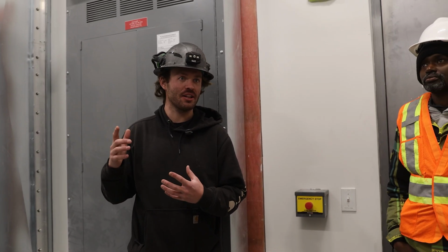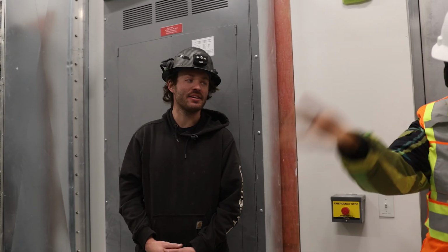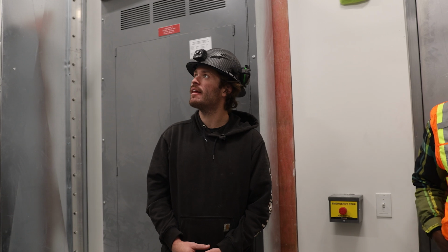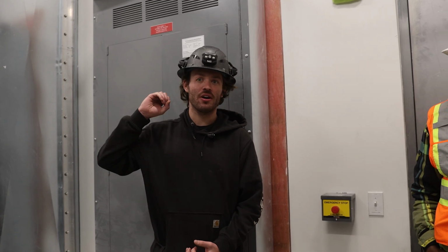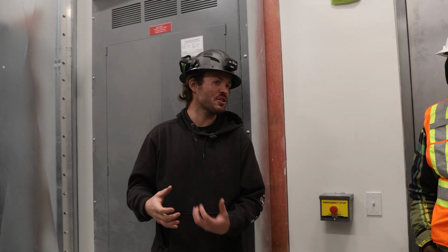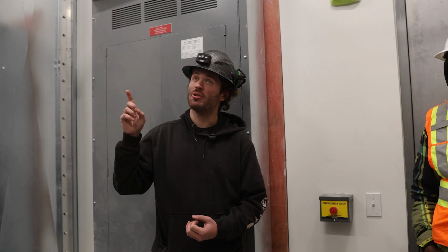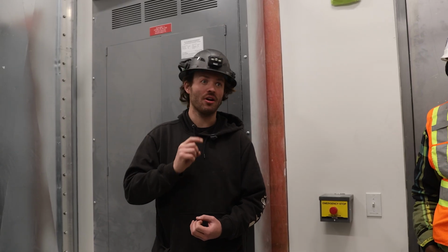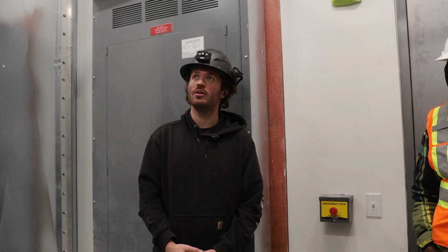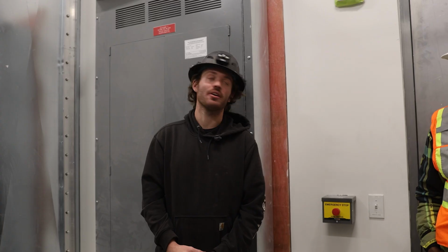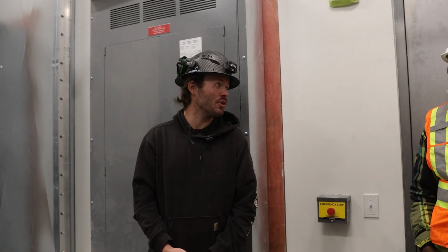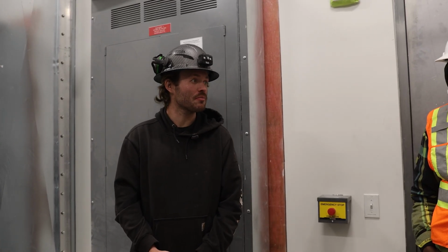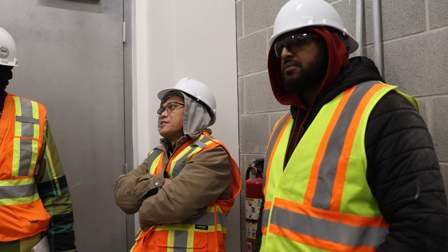I can't remember exactly, one or the other. Let me see. Yeah, taken out. Yeah, that's what I thought. For exhaust. Yeah, so that fan is always drawing air out of the room if there is combustible gas in here. If that fan were to fail, it will throw an alarm. Yeah. So anytime you're in here, you'll hear that thing running. If you don't, your fire alarm should be beeping at you. That's a requirement. Yeah, so just servicing of it, yeah.